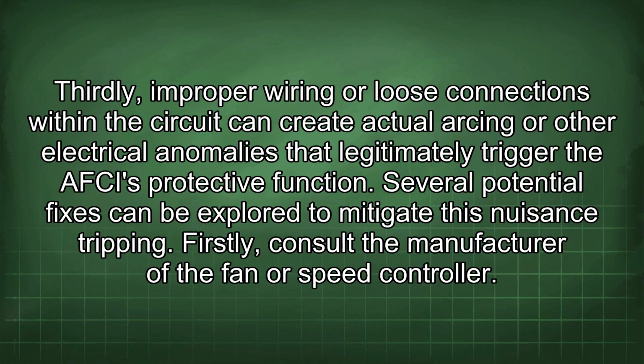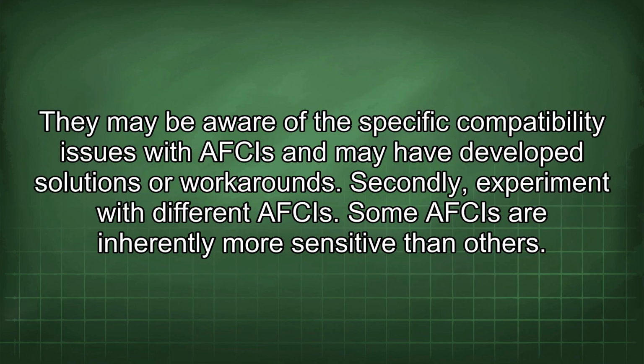Thirdly, improper wiring or loose connections within the circuit can create actual arcing or other electrical anomalies that legitimately trigger the AFCI's protective function. Several potential fixes can be explored to mitigate this nuisance tripping. Firstly, consult the manufacturer of the fan or speed controller. They may be aware of the specific compatibility issues with AFCIs and may have developed solutions or workarounds.